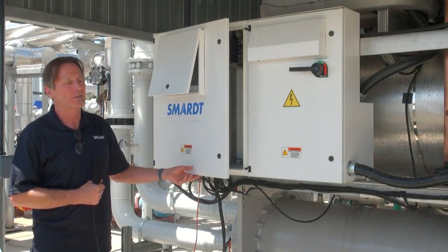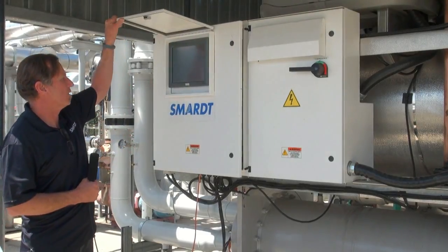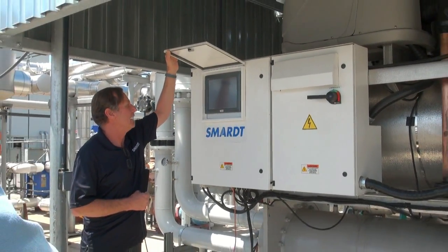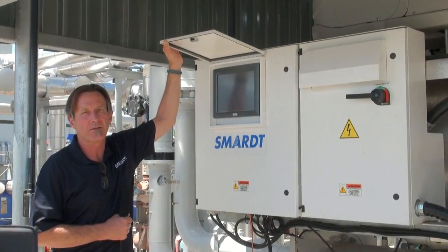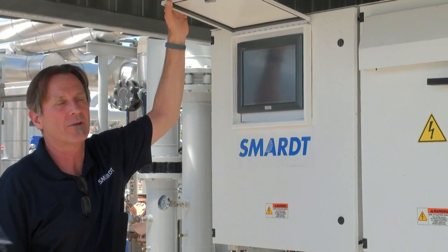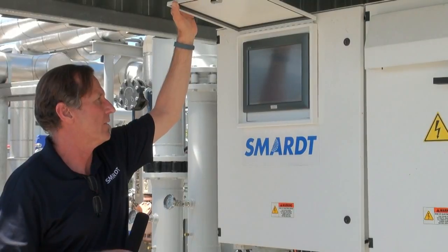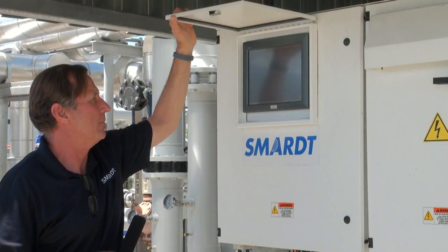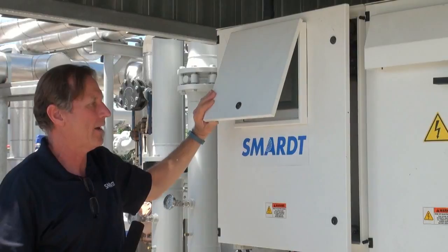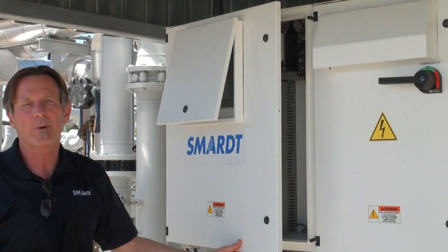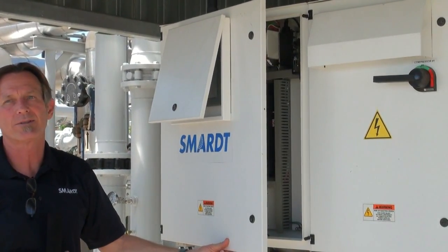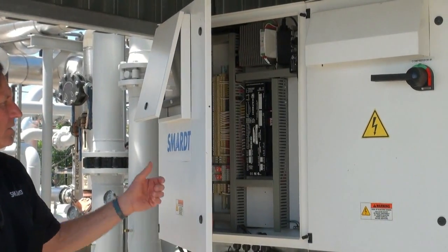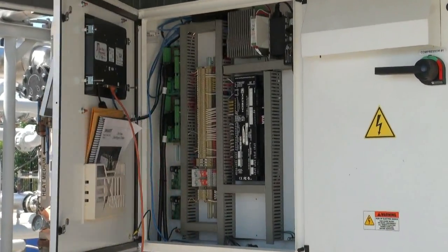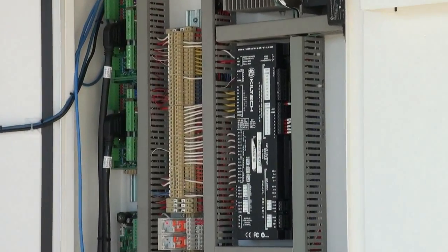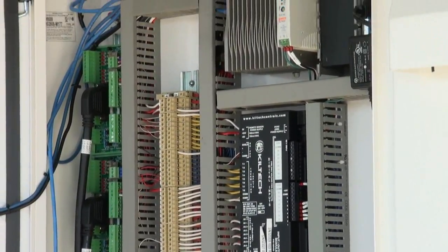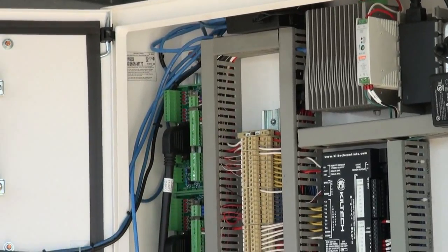Then you have the control panel. On the front of the control panel is a display. It is just a display. It has nothing to do with operating the chiller, except that it's an interface. So you could pull that out and take it home. It's not going to affect the operation of the chiller. It's still going to run. You just won't be able to see it locally. So that's your interface. We can go through that in a little bit, and I'll show you all the different views in the controller.